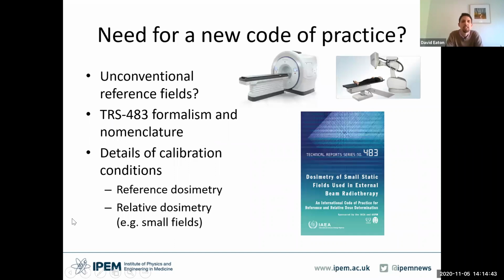So you may be thinking, well, why do we need a new code of practice? The 1990 code has served us quite well for the best part of 3 decades. But in that time, there have been some changes. So in my department at Guy's, we have a tomotherapy unit. There are several CyberKnife units scattered around the country as well. And these are unable to generate a 10 by 10 centimetre field. So the previous code of practice established a reference field size, which was 10 by 10 centimetres. But what do you do if your machine cannot achieve that field size?